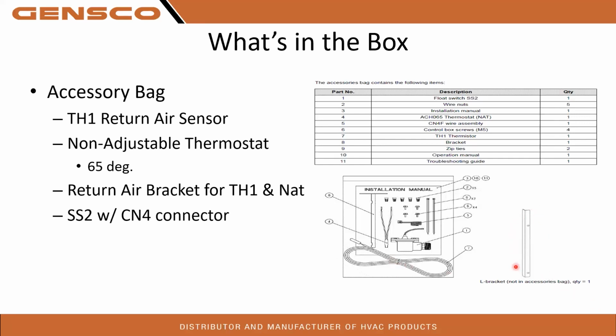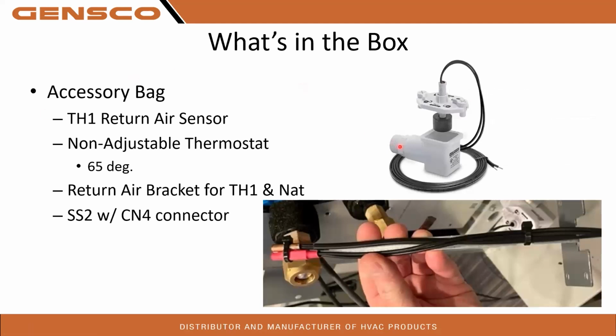Here's that L bracket that we talked about a little bit. Again, that doesn't come in the accessory bag, but it does come with the kit. Here is that condensate safety along with those thermistors that we talked about. Again, the bare copper one here is the return temperature thermistor. The red one is a non-adjustable thermostat.